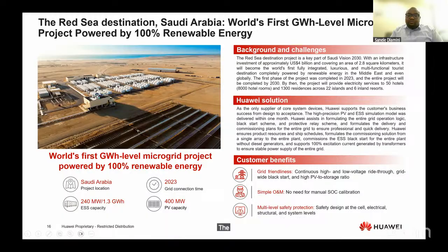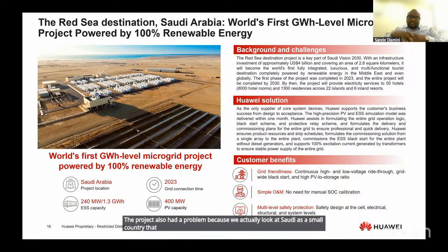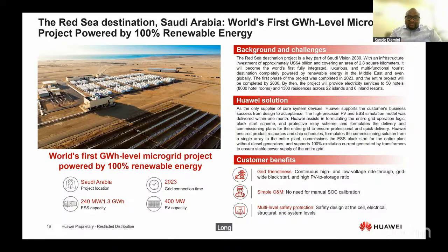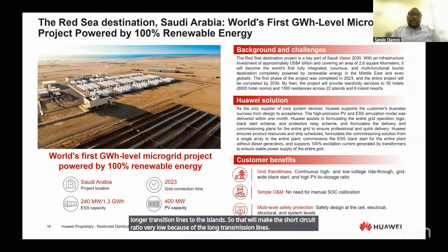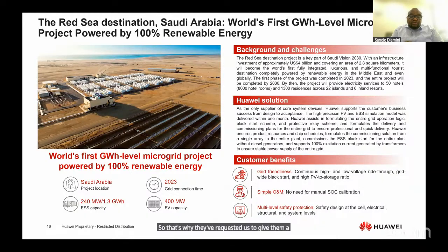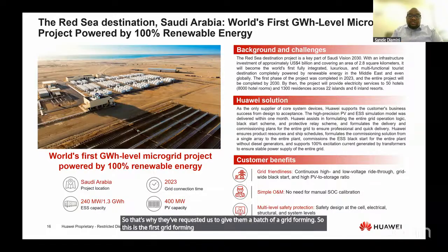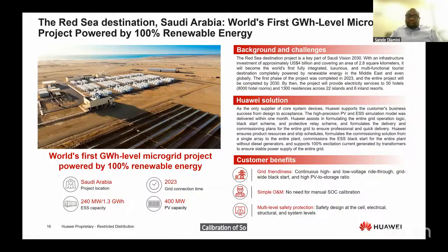The project also had a problem because Saudi is a small country that has got a lot of islands, meaning they have to do long transmission lines to the islands. That makes their short circuit ratio very low because of the long transmission lines. That's why they requested a grid forming battery from us. This is the first grid forming microgrid we did in Saudi Arabia for them. You can see the customer benefits: grid friendly and simple O&M, because our battery can do calibration of SOC automatically, and we also do multi-level safety protection.